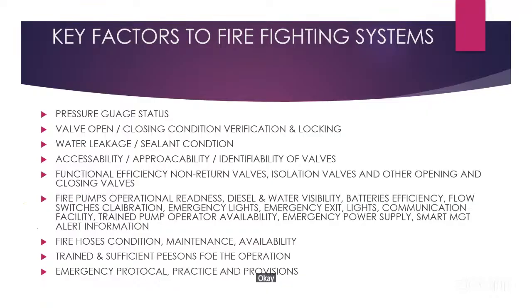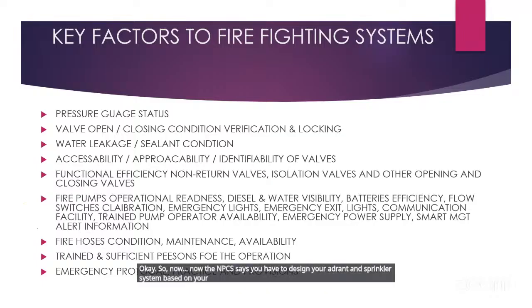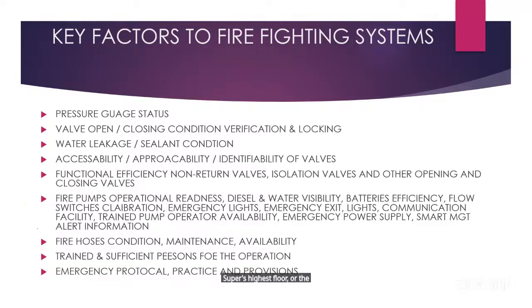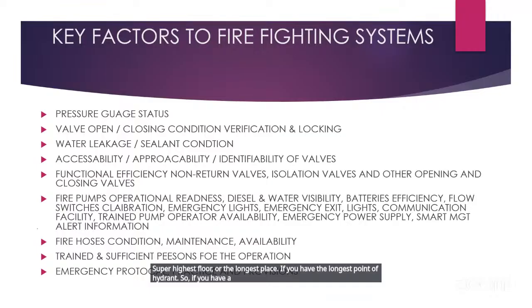Okay. Now the NBC says you have to design your hydrant and sprinkler system based on your hydraulic calculation only. It is not like NBC 2016. It was just telling you that at the remotest point, if you have 3.5 kg, that is enough. Suppose the highest floor or the longest place, if you have the longest point of hydrant, and you have 3.5 kg pressure, that is quite sufficient as per the NBC 16.